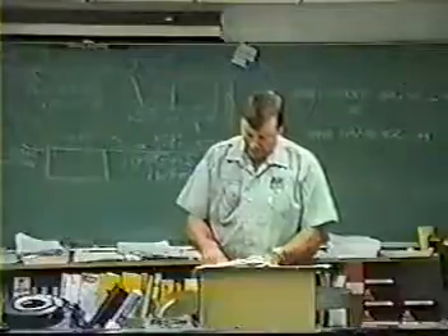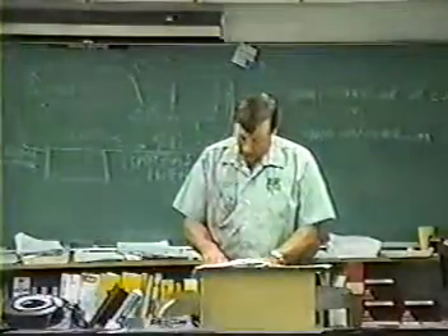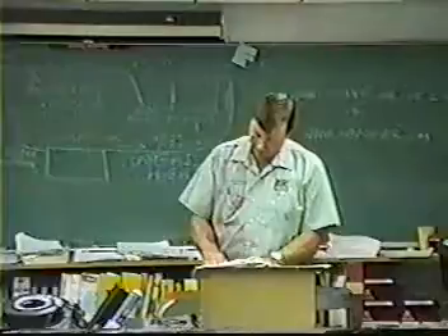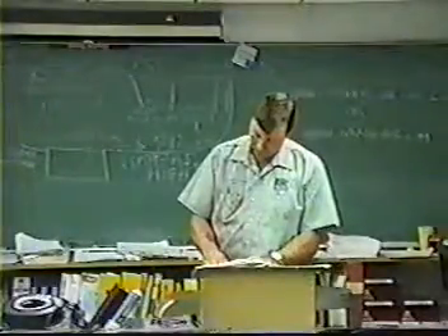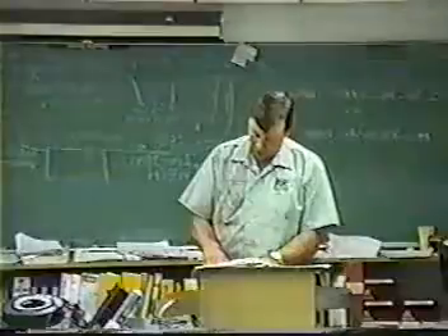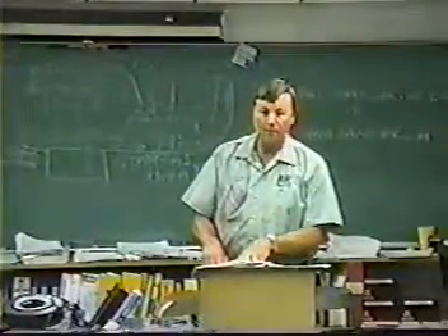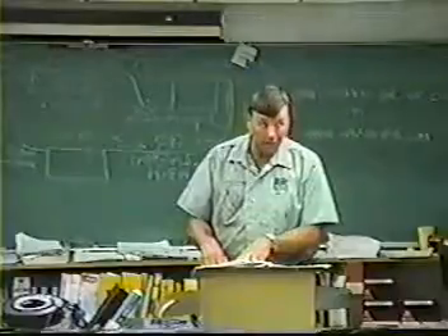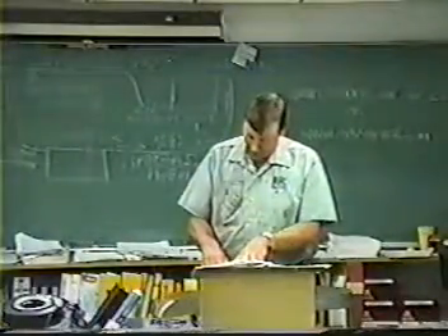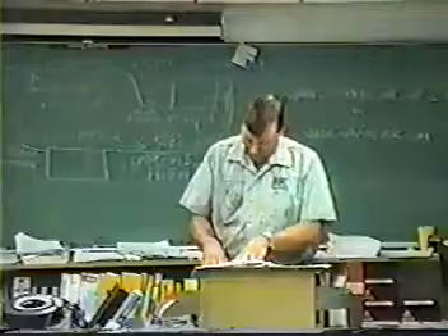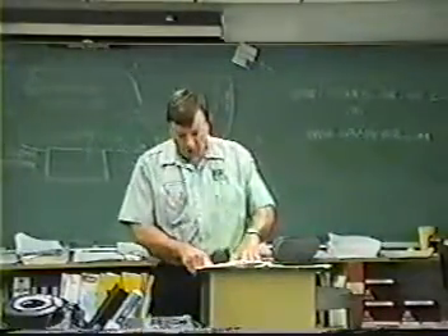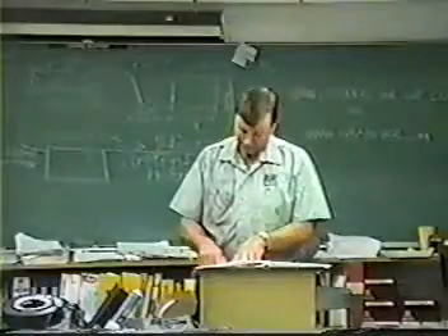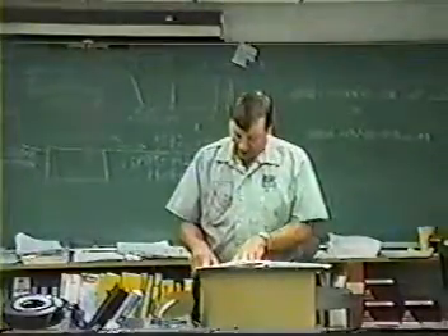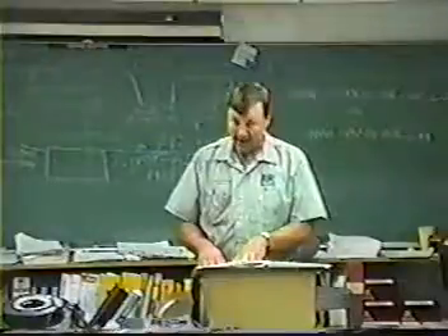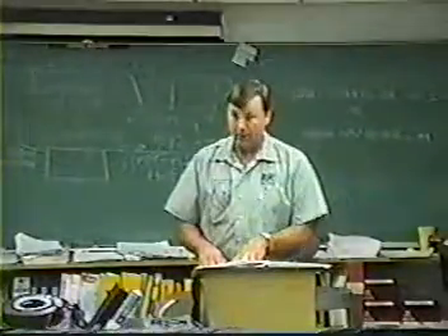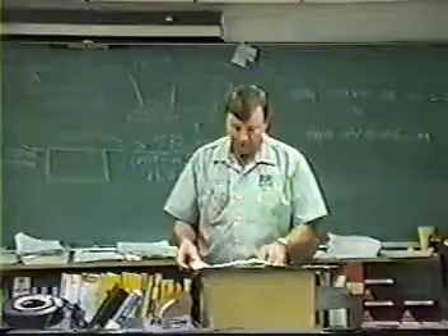Type 2 classification, as identified by EPA, applies to what equipment? Split air conditioning equipment with 5 pounds of refrigerant and greater. We know that less than 5 pounds is type 1, right? Okay. C is low pressure appliances. That's going to be type 3. B, refrigerator, freezer, and vending machine appliances. That's going to be type 1. Small appliances with 5 pounds of refrigerant and less is going to be type 1. So the only answer would have to be D by elimination. That's the only answer it can be. Okay, move on to number 55.